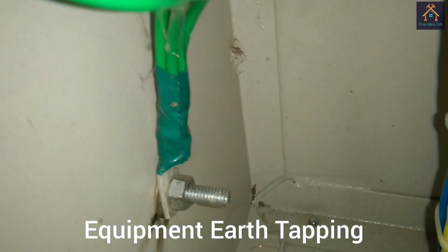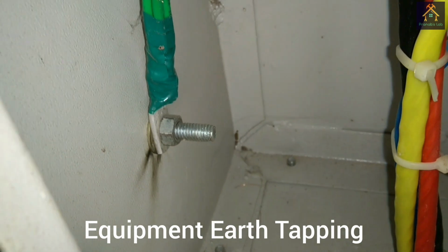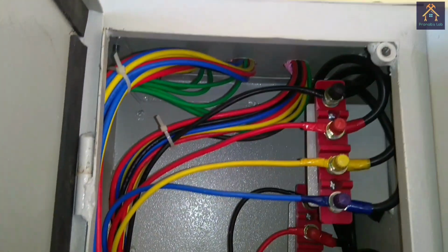And here you can see the green cables coming out from a point. I think this is the earthing point, and yes, this is the earthing point, and the cables are connected together with a lug and nut bolt with the panel, and with each way each earthing point is also run through the conduit pipes.